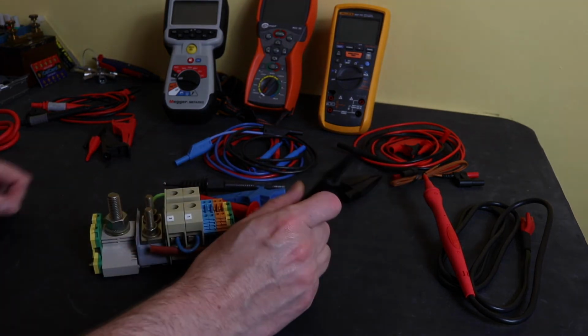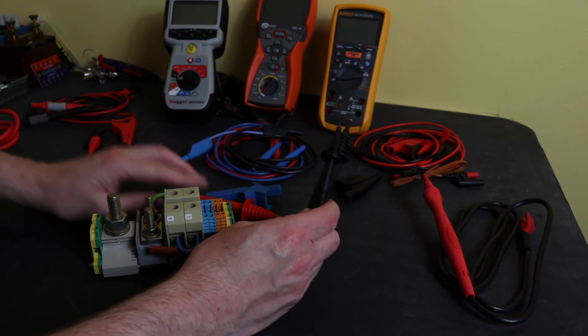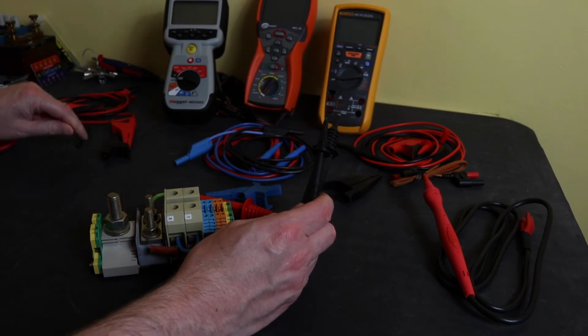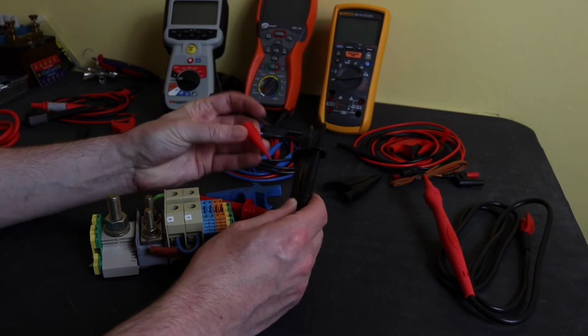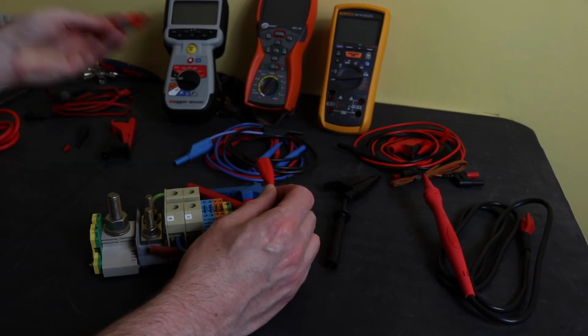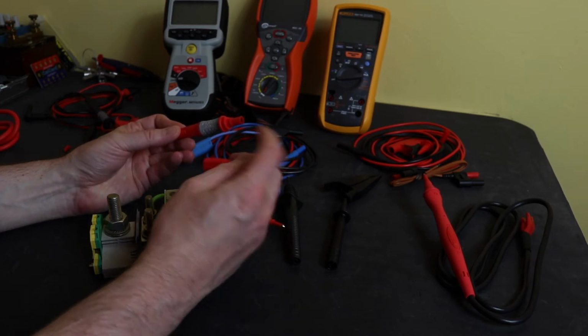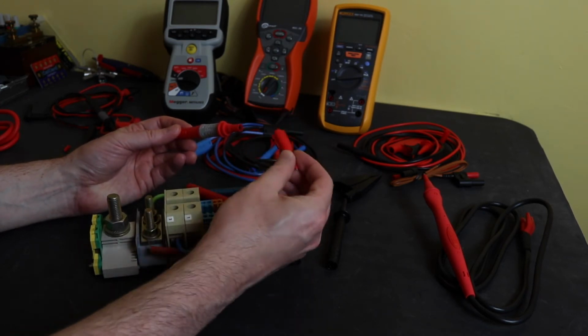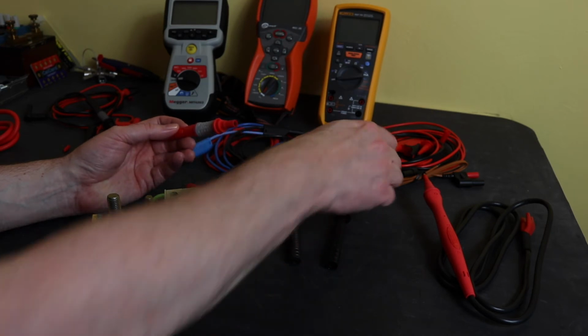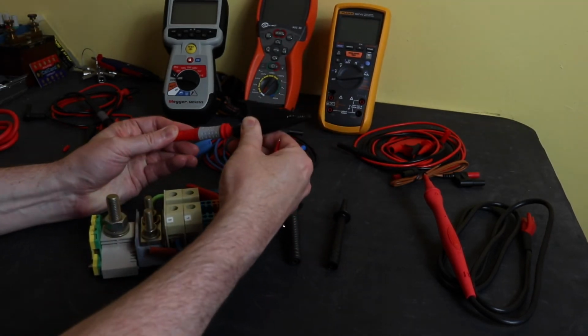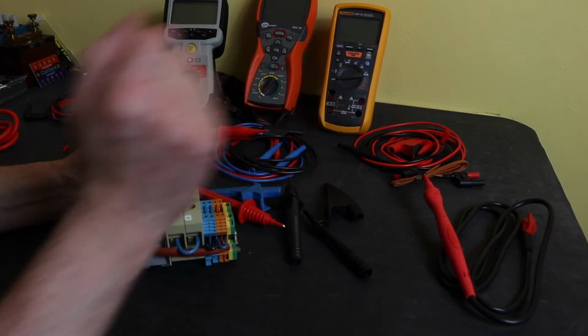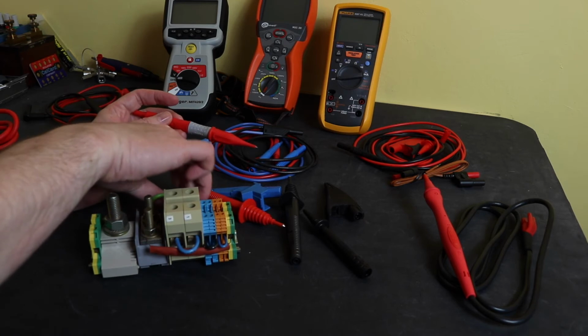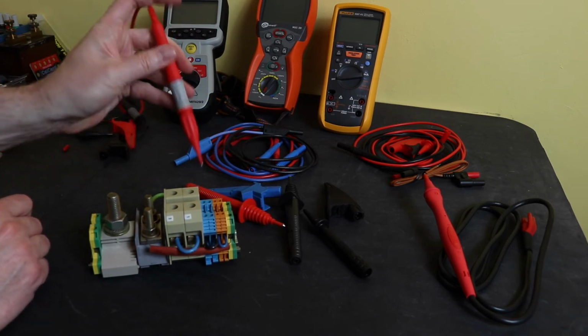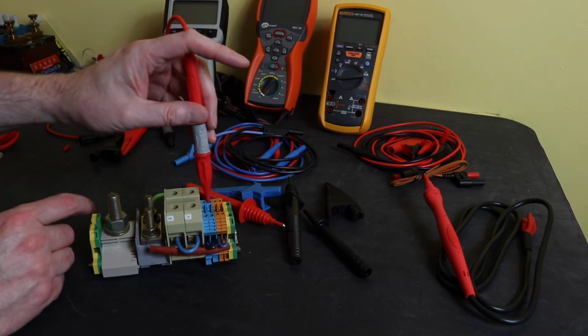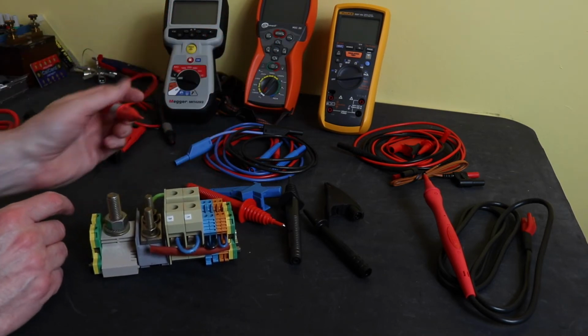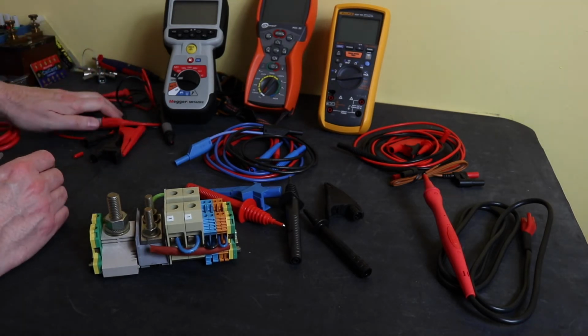In terms of probes, all of them have red and black probes that come with it. There's the Megger. Obviously we've been down this route before if you've seen the other videos. It's a bespoke connection on the Megger for plugging the probe tips onto, so you can't plug a standard 4mm accessory in. It just doesn't go over the clip in the same manner that the probe does. These, as I said before, are some of the nicest probes. You'll easily gain access to the smallest of terminals, no problem whatsoever. Very, very nice probe from Megger there.